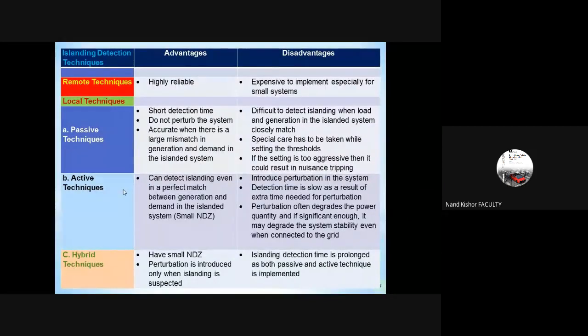Then the active techniques, if you refer, can have detection even when you have a perfect match of power between the generation and the demand, and that we call the non-detection zone. Actually, this is the NDZ word we use here. But the disadvantage includes that we need to perturb the system. Detection time is slow because we need more time for perturbation. And as I said earlier, because of the perturbation, it may degrade the power quality. And again, it may also significantly impact the system stability when it is connected to the grid. That is one consequence you have to bear if you have the active technique, and thus it will be a disadvantage here. And the last one is the hybrid technique.